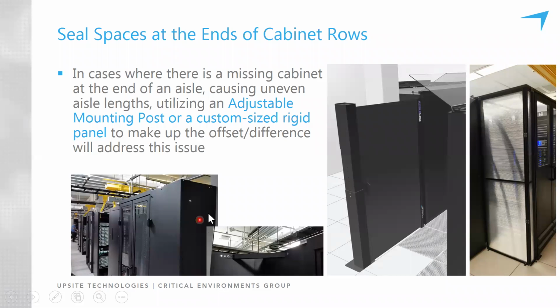You can't see the building column, but it's another one of those big white columns you saw in the previous slide. So we designed a steel enclosure to span the rest of the aisle and return back to the column. And inside, where you've got the 90-degree angle, there's a brace so that when these doors close, it doesn't wobble or shake, and it adds to the structural integrity. In the larger picture in the middle, Upsite has a unique way of addressing this situation as well. This is called an adjustable mounting post. It's a rigid metal post with a big steel plate that you can mount to the floor, and you can position this post to align with the cabinet on the other side of the aisle, or whatever piece of equipment it might be. Now you've created that common plane or alignment that you need to properly attach the doors and make them work.